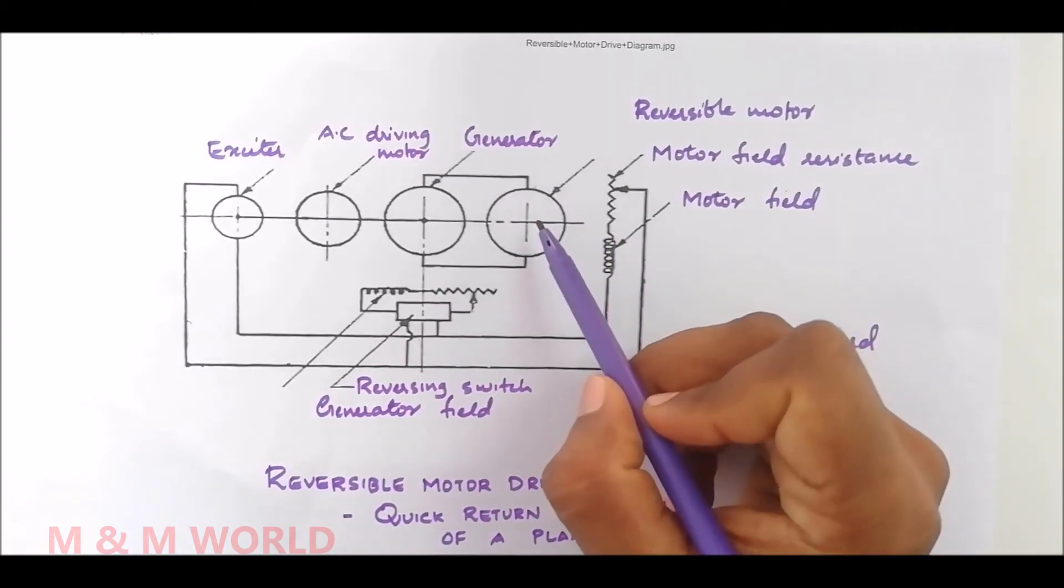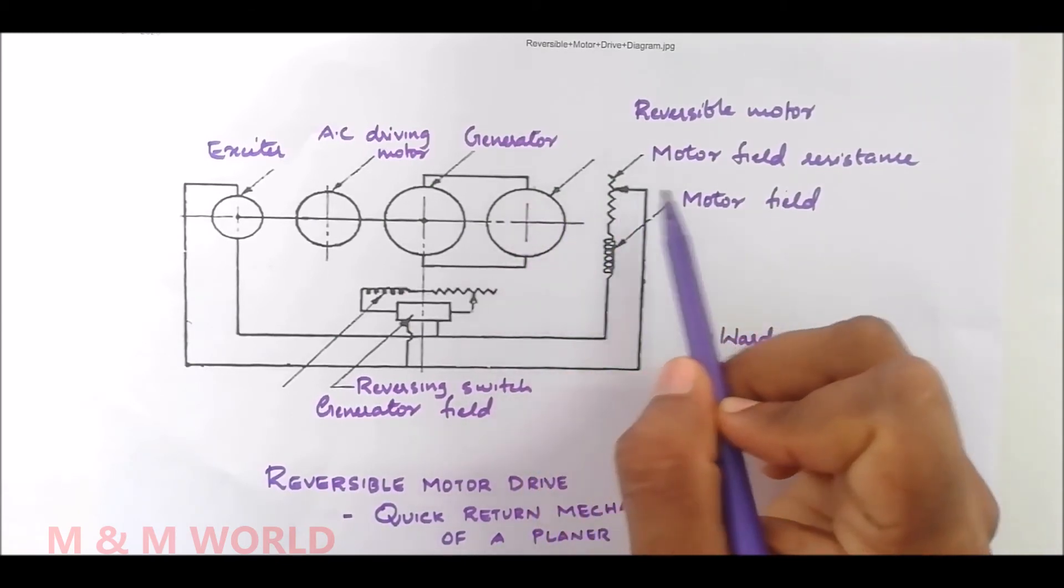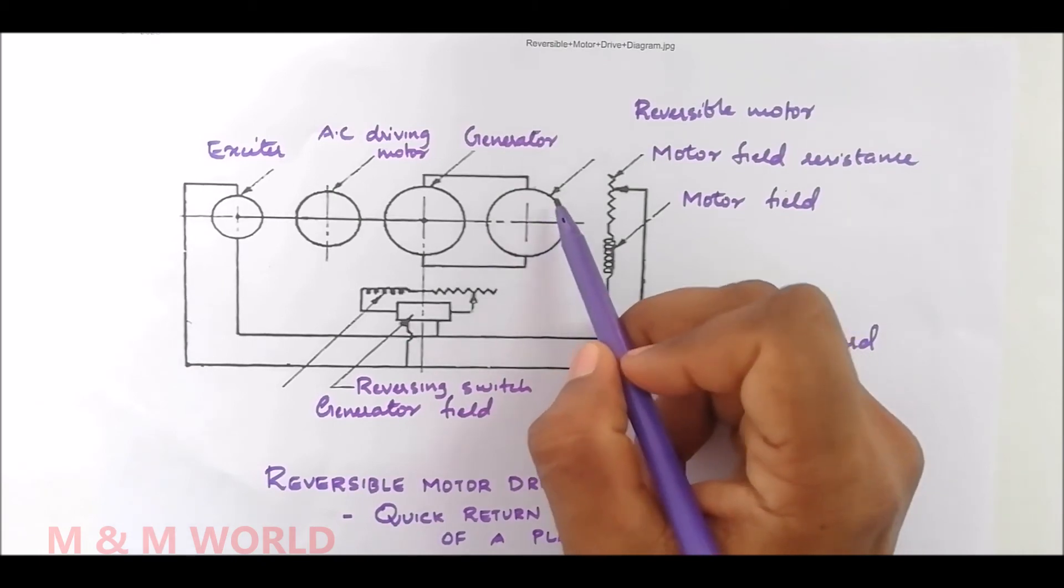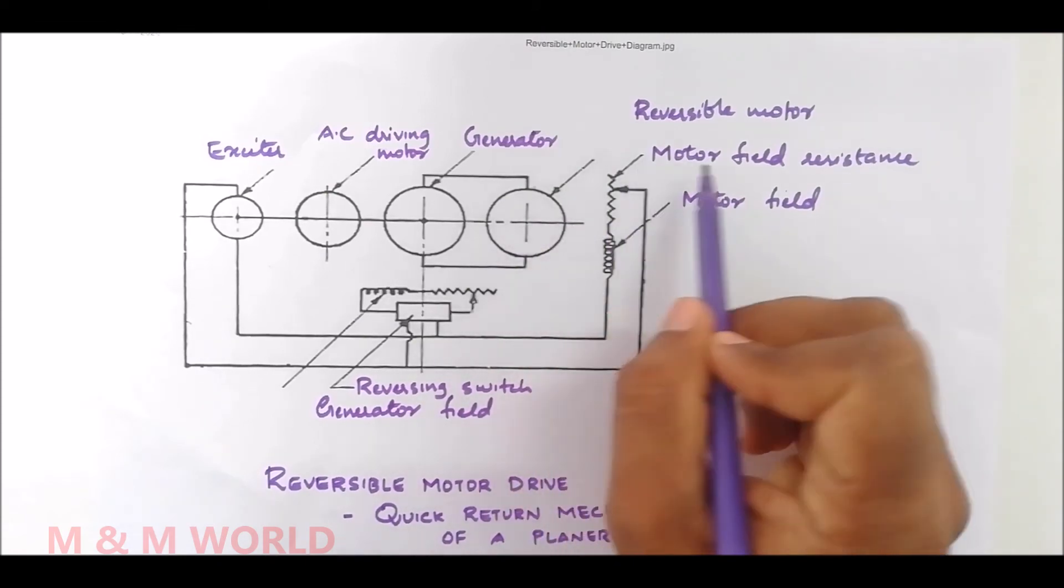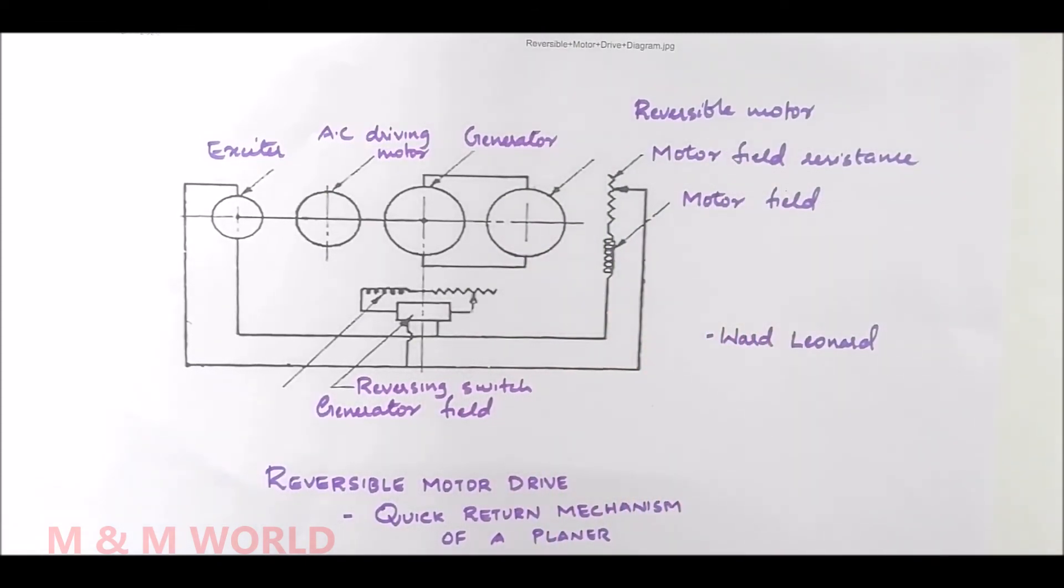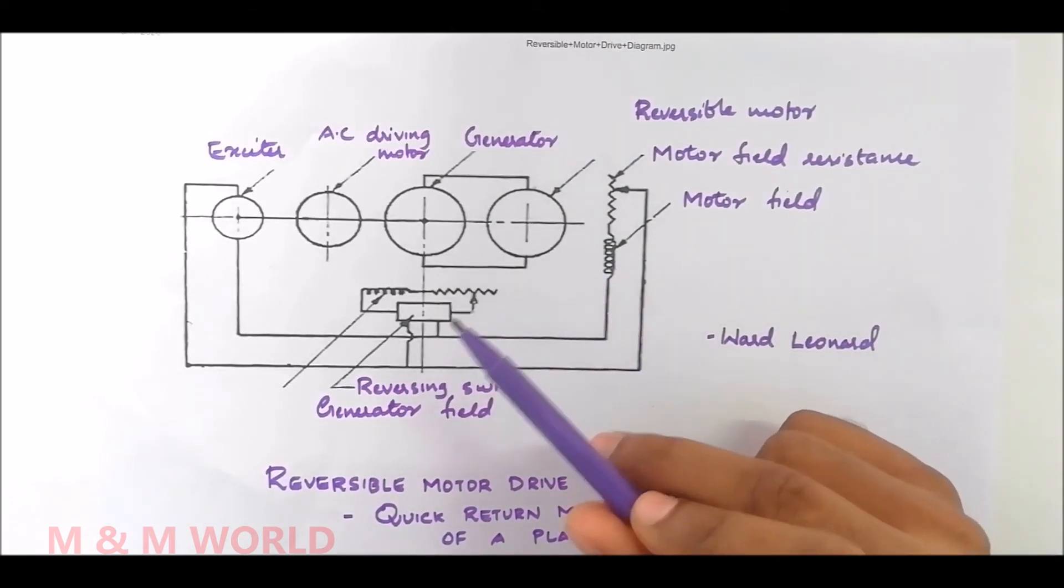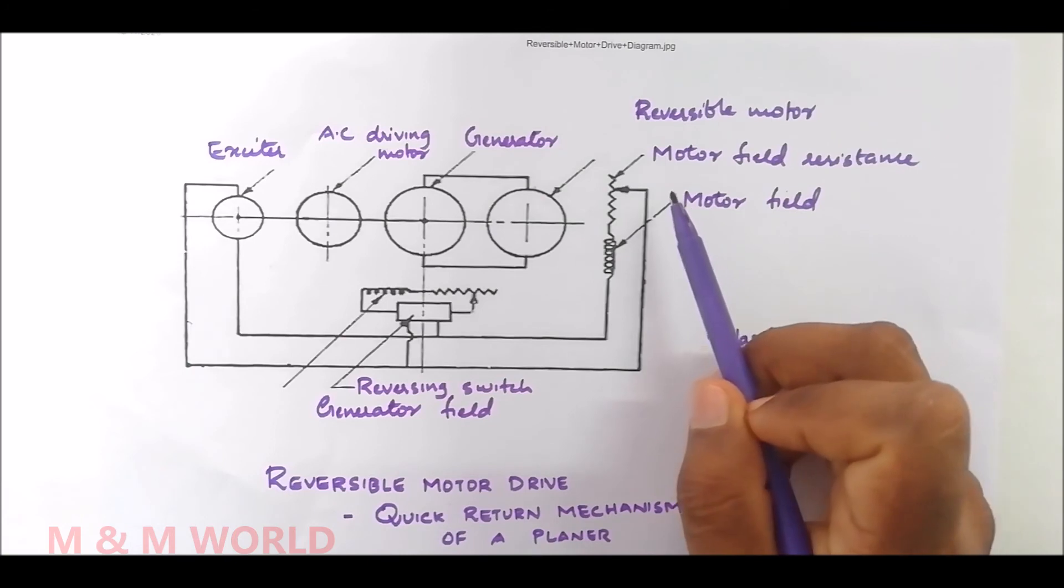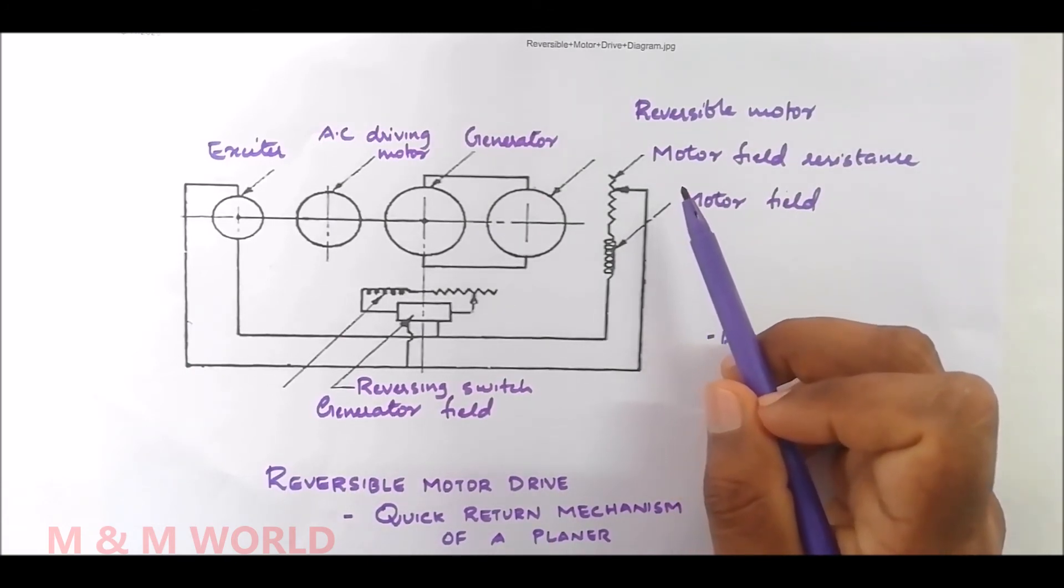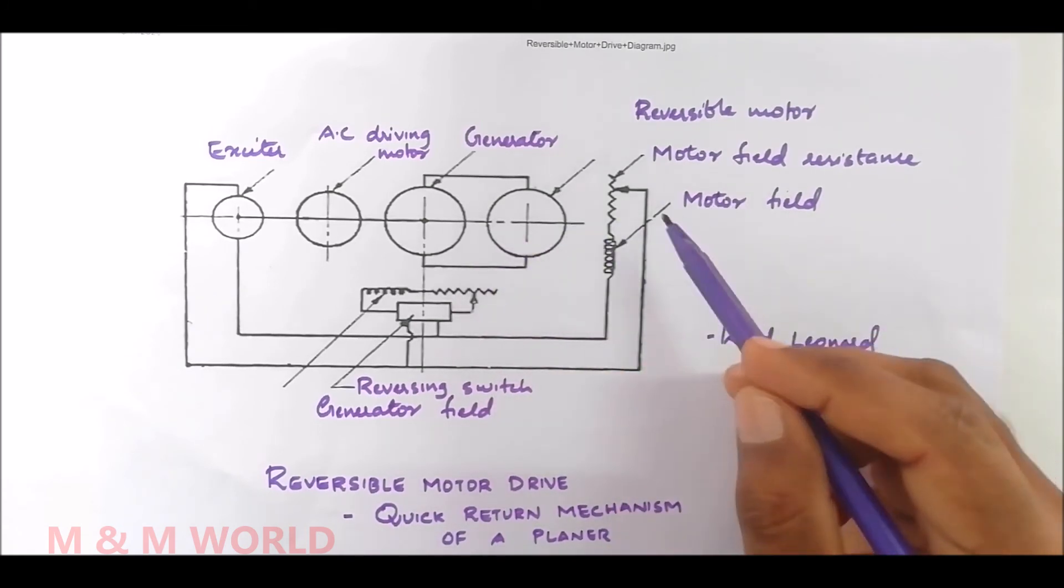This causes the motor to rotate in opposite direction, causing the planer table to reverse. The speed during cutting stroke may be made slower than the return stroke by regulating the field current of the generator and the reversible motor with the help of resistance.